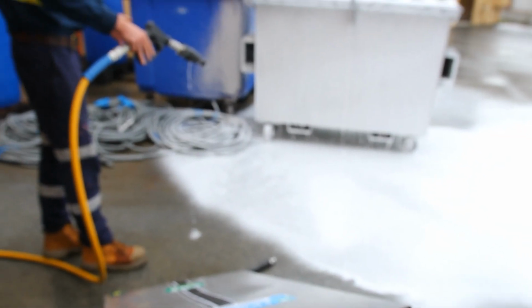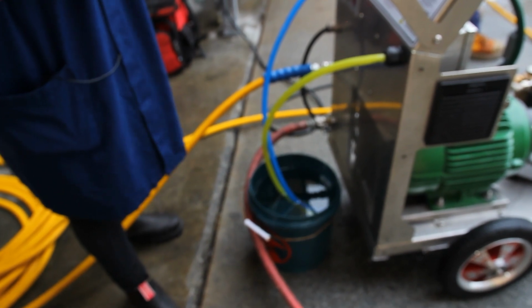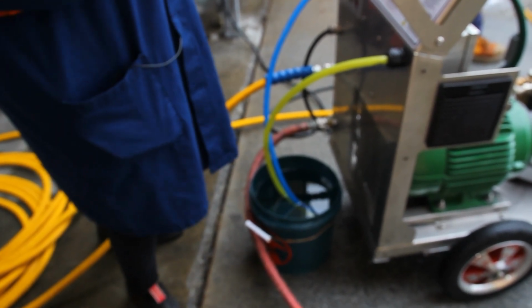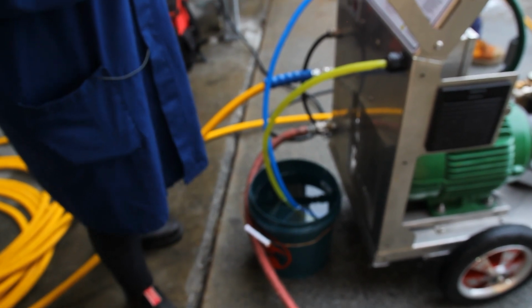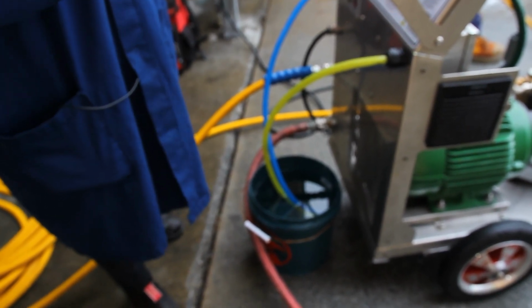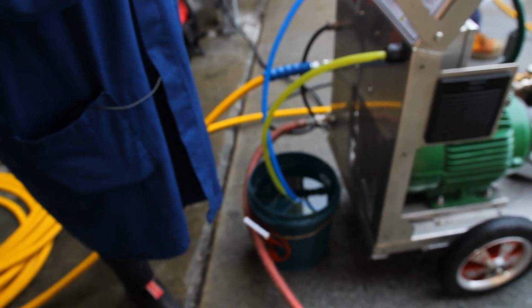So what we're going to do now is run water through the chemical line where we just sprayed. We actually sprayed it with an acid detergent. So the idea of this is to keep the line clear, the check valve clean, and the nozzle at the end of the hose clean. Most cleaners don't rinse anything out, but I'm going to show you how it's supposed to be done. So we're going to move from the bucket to the water, turn the machine on, and then you'll see at the other end the nozzle rinse clear.